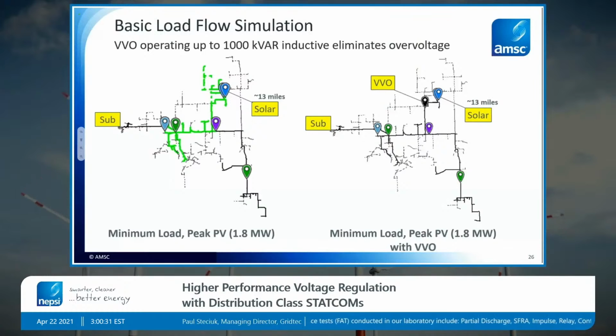So we have a solar plant coming in approximately 13 miles away from the substation. So here's the substation, here's the overhead feeder, and on this branch circuit is a solar plant that is 1.8 megawatts. There's a couple of voltage regulators on the circuit existing. And what this is showing is that these light green areas are over voltages on the circuit due to that solar being at full output at the same time that it's lightly loaded, like a spring condition. On the right is a load flow in CYME showing that the VVO totally eliminates that over voltage. So you see the light greens are totally addressed there.